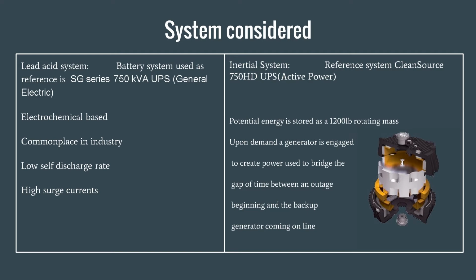For our inertial system, we chose Active Power's 750 HD UPS because it's a comparable system. An inertial energy storage system consists of a large rotating mass inside a vacuum chamber, supported by magnetic bearings and kept spinning by an electric motor. If the power goes out and electricity is needed, a generator is engaged and power is drawn off. These systems provide a large amount of power in a very short period of time, just enough for a backup generator to come online.